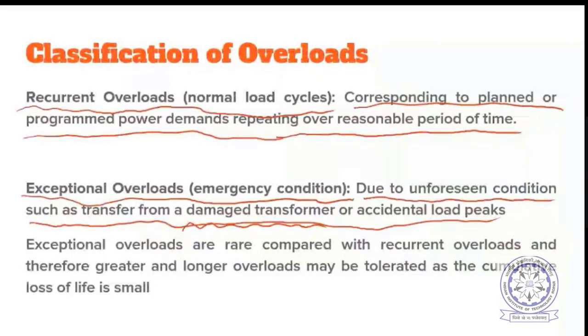So what immediately is to be done is that the line has to be disconnected, and the load corresponding to that transmission line will be shifted to another transmission line where another transformer will exist. So that transformer to which the load is transferred will definitely be overloaded. But this is an emergency condition, not expected, not a planned condition. So this is known as exceptional overload again.